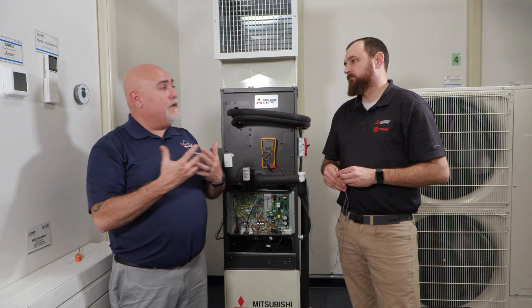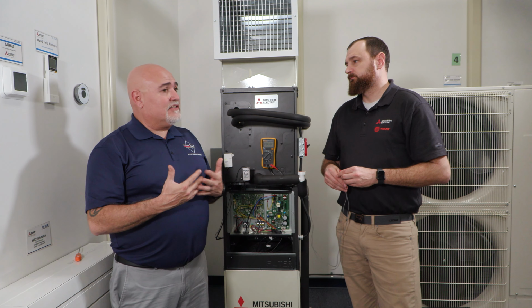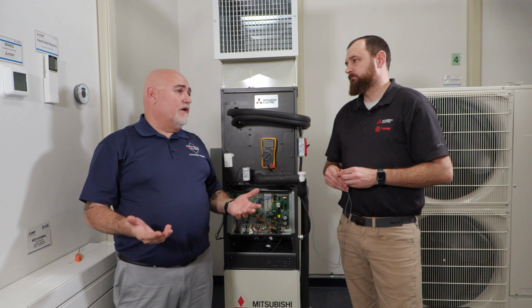Okay. Is it possible for both the motor and the indoor board to be malfunctioning or defective? Yes, absolutely. But we can do some checks and see if that rotational feedback is actually reaching the board. Okay. So if the motor is putting out rotational feedback and the system is still throwing a rotational feedback error code, the indoor board may not be interpreting the rotational feedback. So in that case, we're replacing the board.